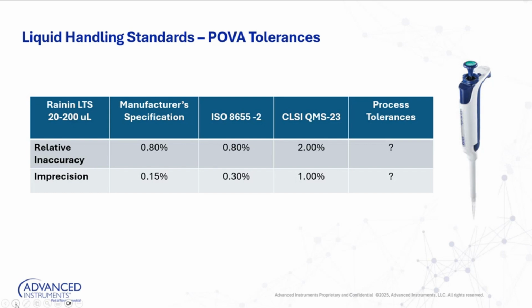So for example, if the laboratory process indicates that this pipette can deliver plus or minus 5% from an accuracy standpoint, maybe you don't need to meet that Rainin spec or that ISO spec of 0.8%. If that range during its true process is plus or minus 5%, 0.8 is probably a little too tight. Maybe you decide to have your calibration follow plus or minus 3%. So it's well within that plus or minus 5% process tolerance, but certainly a little bit tighter.